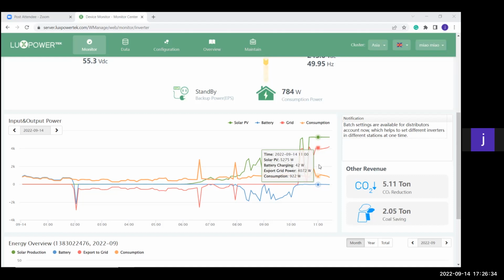The batteries were charging at 42 watts. That's the bus voltage that's active constantly. He was exporting to the grid. He has a house with a workshop, so all the power that's exported from his house's system goes into the workshop and is being used by the workshop. It never reaches the grid, this client. And then the consumption on the inverter was 902 watts. So this graph gives you just an estimate of what was happening on the inverter at a certain time range.